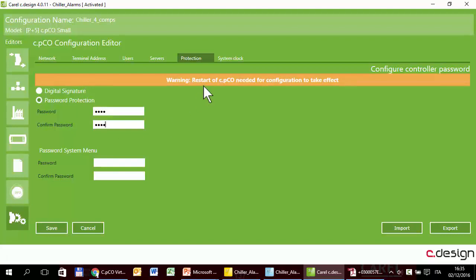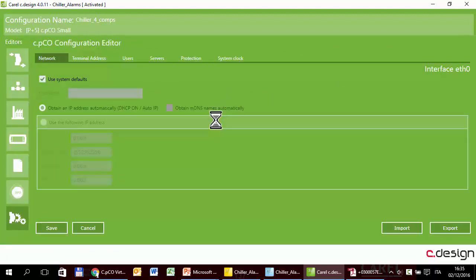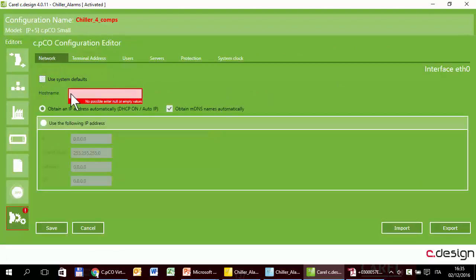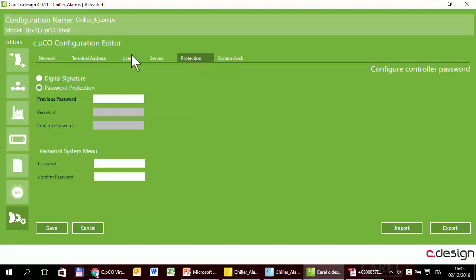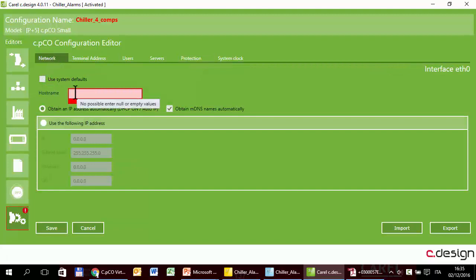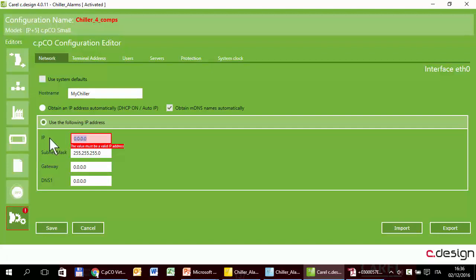This message states that once this configuration is uploaded and the password is changed, I have to restart. So 1111. Save. Actually, I have to also edit the network settings, else I will lose the IP configuration. Because if I leave 'use default' and upload this configuration, I will upload not only the password but also that setting, so I will lose the current IP configuration. I will set the IP to 10.10.1.2.